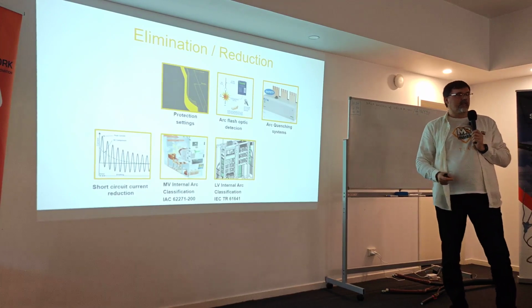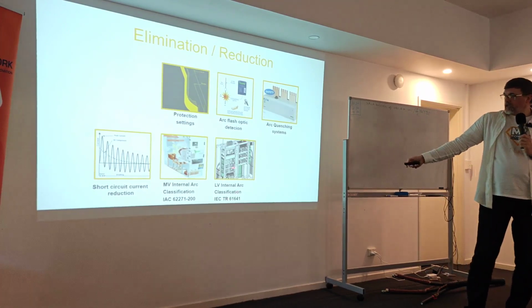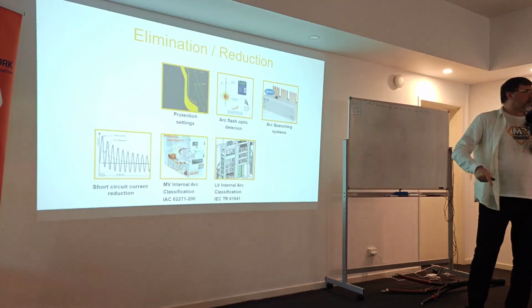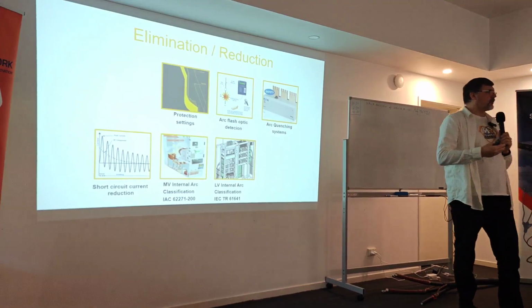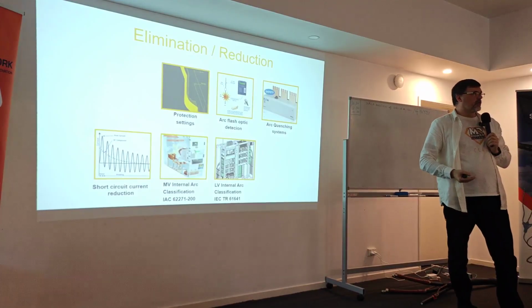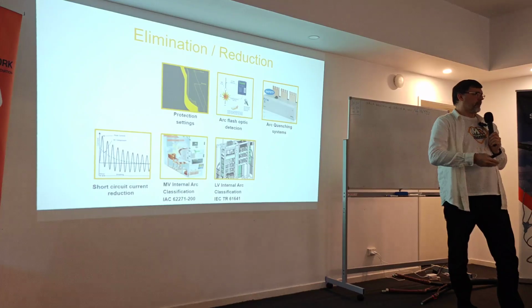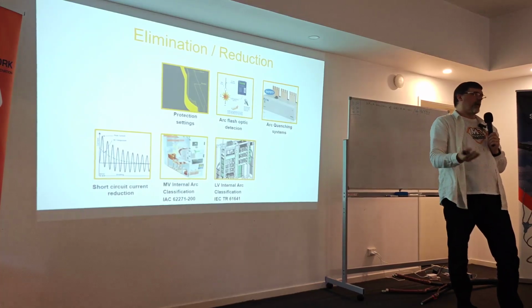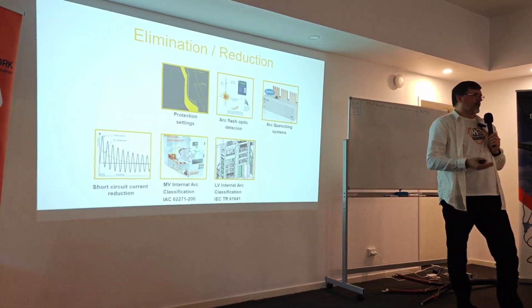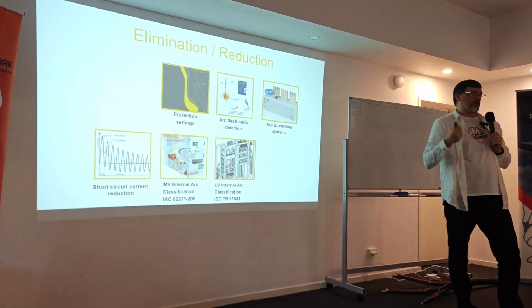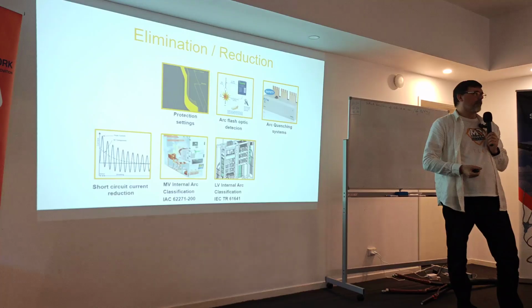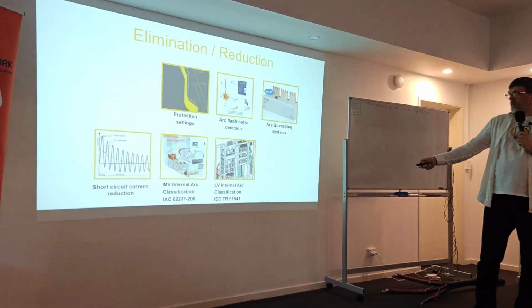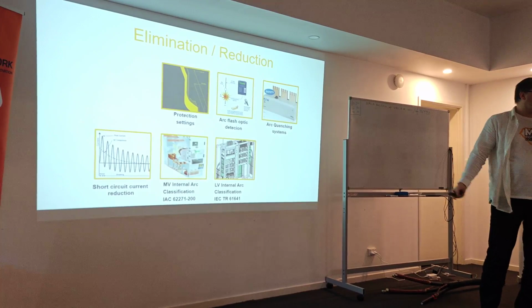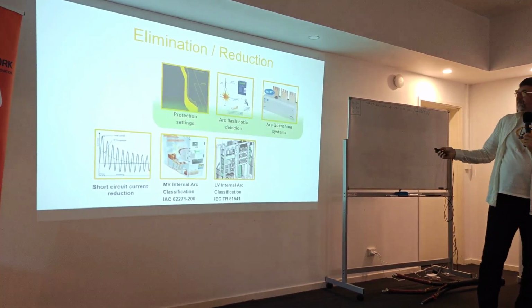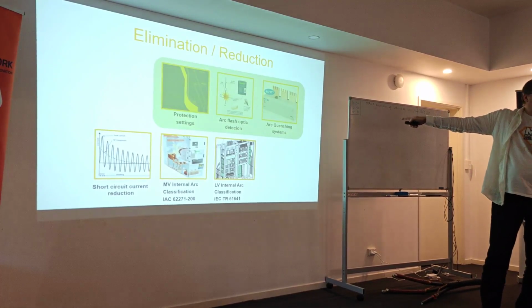So everything we need to understand how to use, yeah? The same thing exists for the low voltage, but it's just less popular. In low voltage panels, it's very typical that when you do something, you will just open it, yeah? In medium voltage, it's rarely possible to open panel when it's energized. There's a lot of locks that you can of course bypass if you know how it works, but it's very hard to open panel when it's energized. In low voltage, it's like we will keep opening this, yeah? So it's a very rare thing because once you open the doors, your arc rating is gone pretty much. So we look on those three things later.